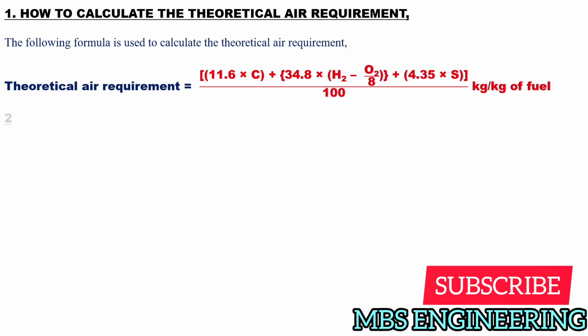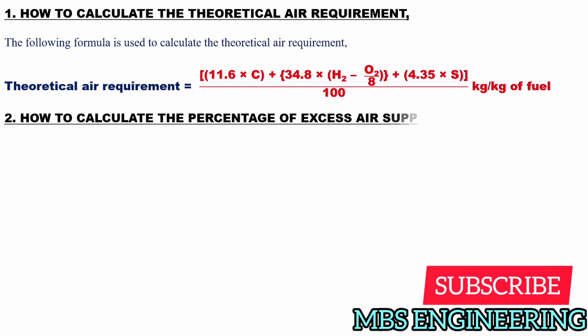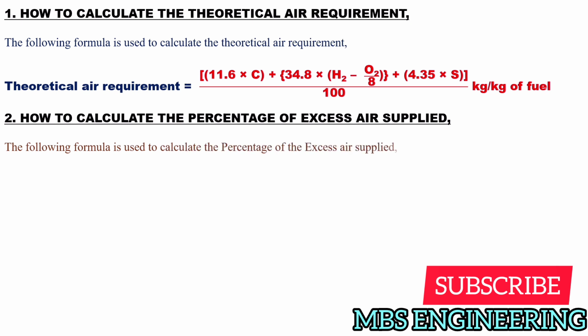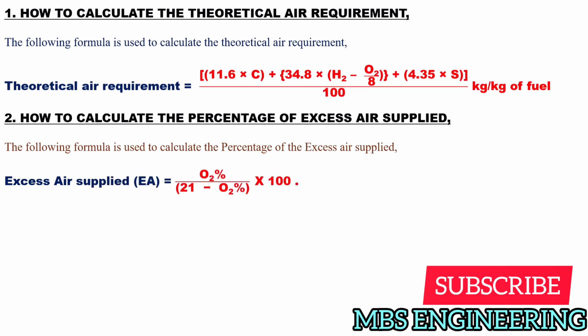Next, we will learn and understand the formula used to calculate the percentage of excess air supplied. The following formula is used to calculate the percentage of the excess air supplied. Excess air supplied, EA, is equal to O2 in percent times 100, and then the obtained value is divided by 21 minus O2 in percent.